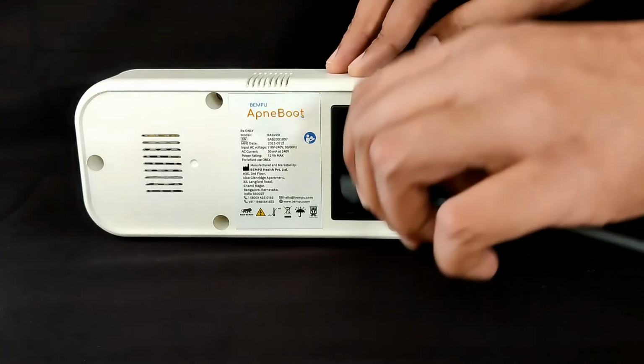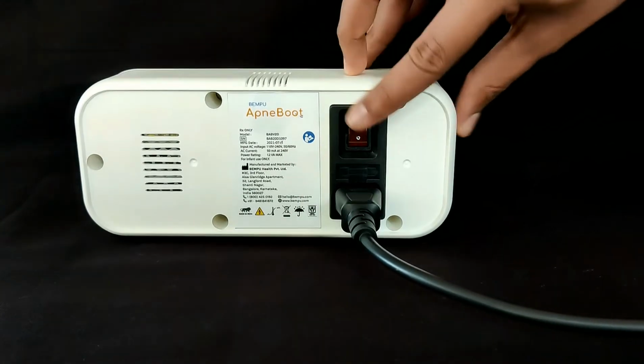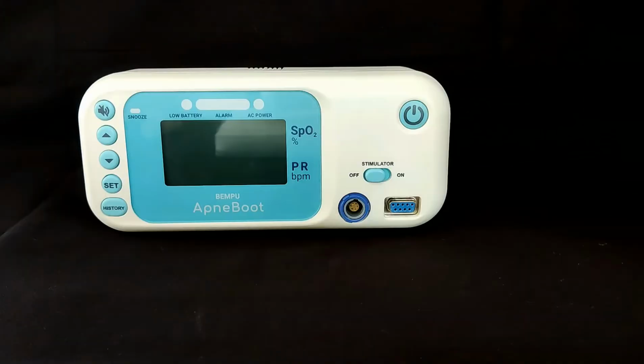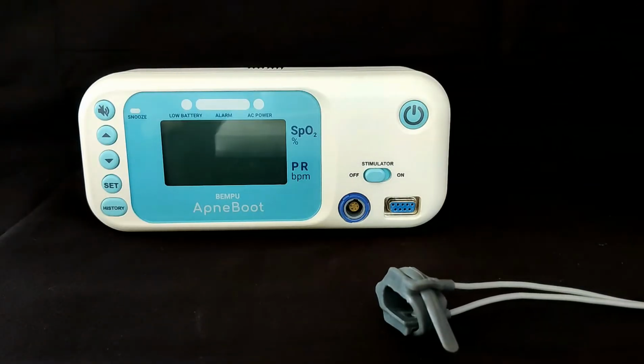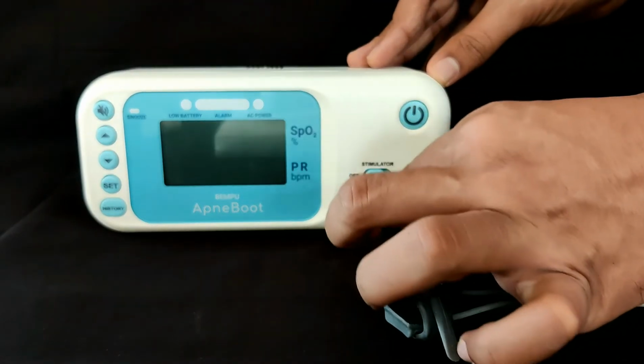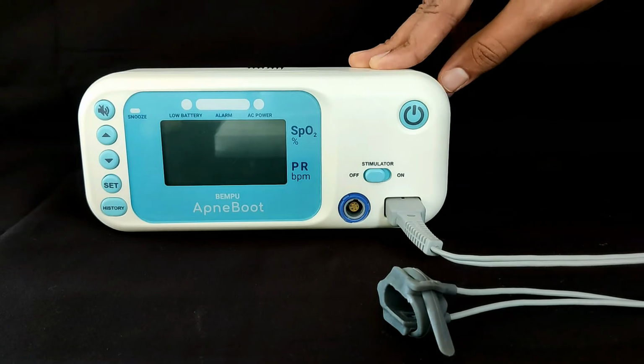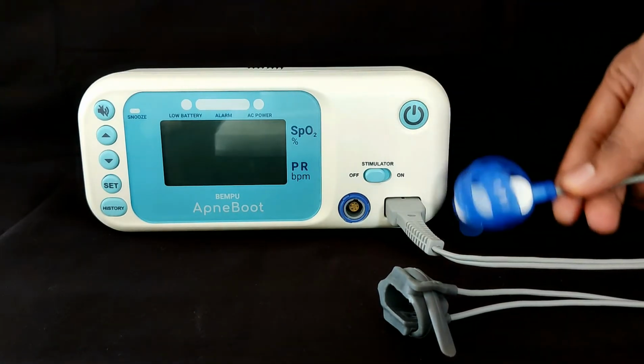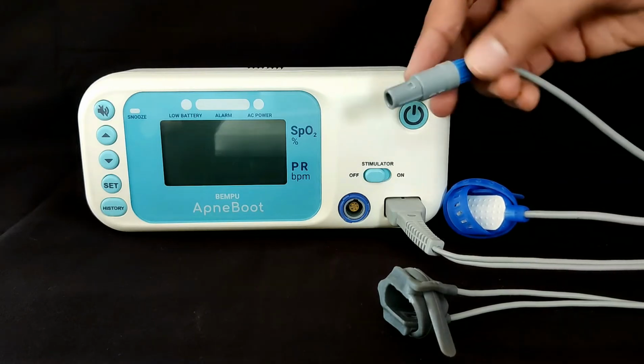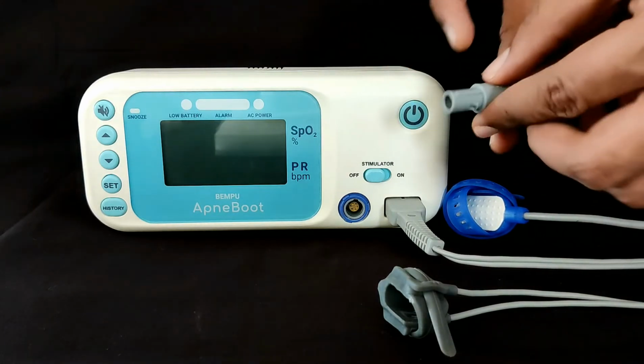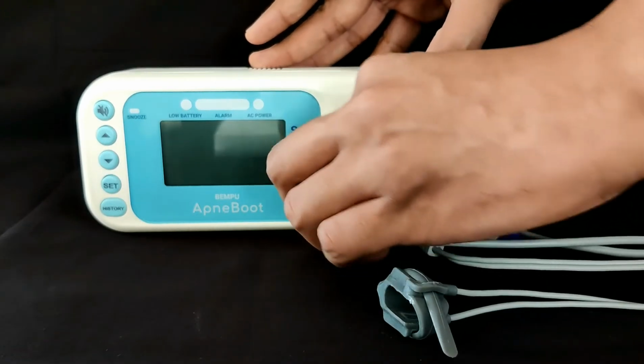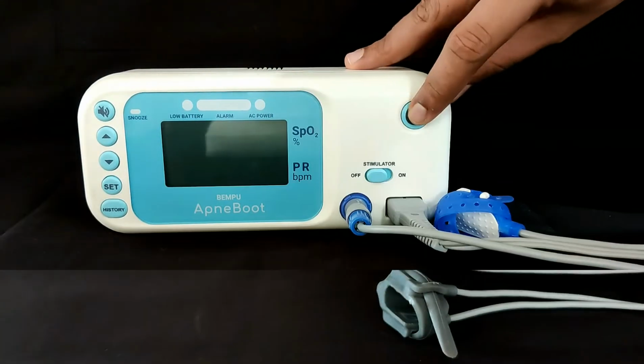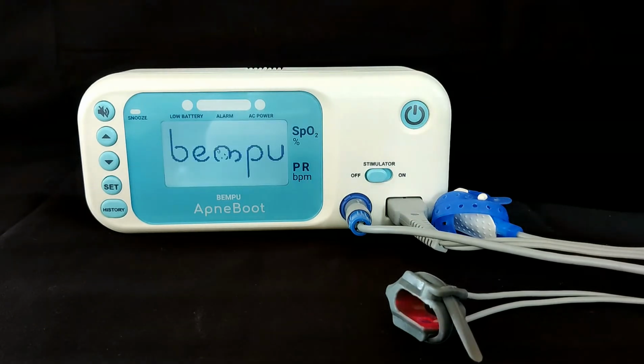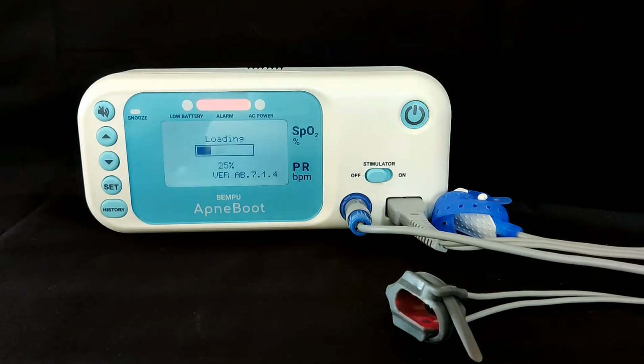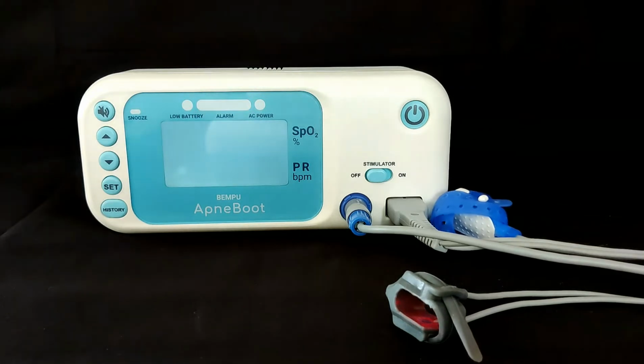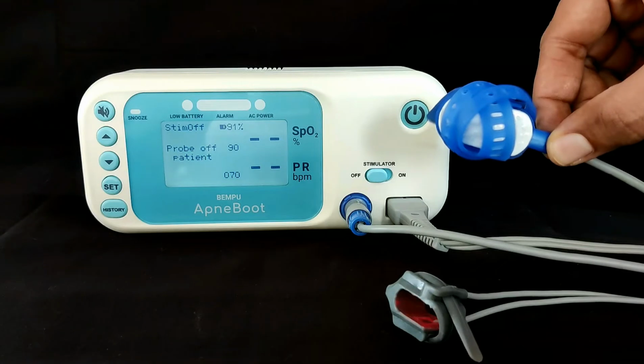To use the device, connect the power cord and turn the AC switch on. Then plug the pulse oximeter probe into the connector. Make sure to firmly push it in. Next, connect the foot stimulation probe into its connector. Make sure you match this notch on the probe to the slot here. You will hear a click sound indicating the probe is connected correctly. Press the power button on to turn the device on. A setup screen will appear. The alarm will turn on, all LEDs will blink, and the foot probe will stimulate once as part of the device startup sequence.